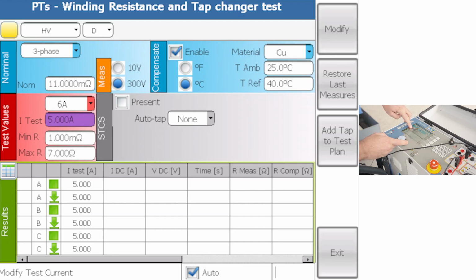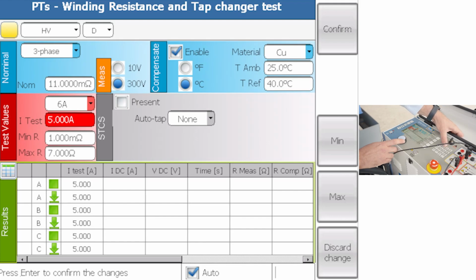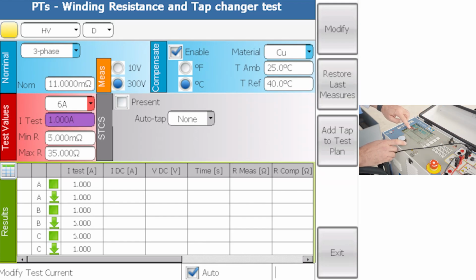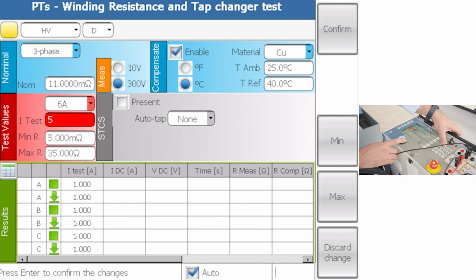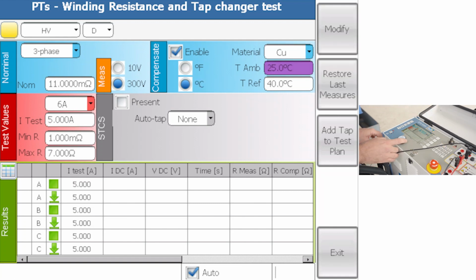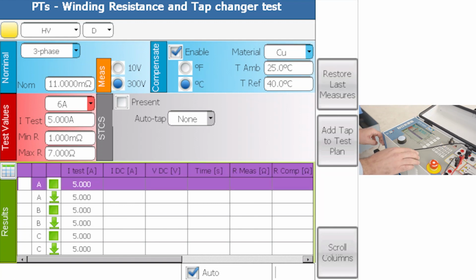I will generate 5 amps, and by the way, with 5 amps, the minimum resistance you can measure is 1 milliohm and the maximum is 7. If I were to change this to 1, you will see these numbers changing. So then we will generate, the minimum resistance would be 5 milliohm and the maximum 35 ohm. But as we said, let's generate 5. I choose once again the phase I'm measuring and I press start.